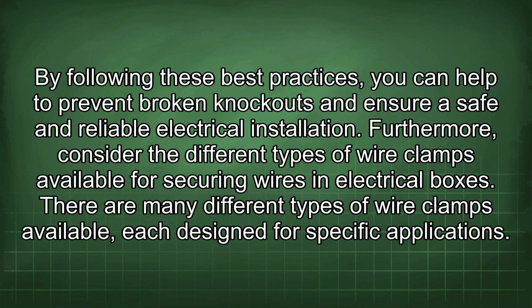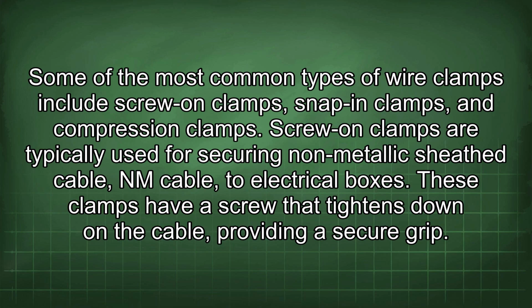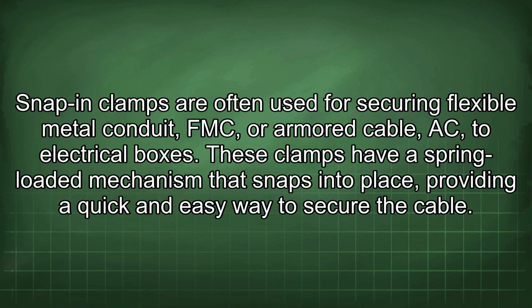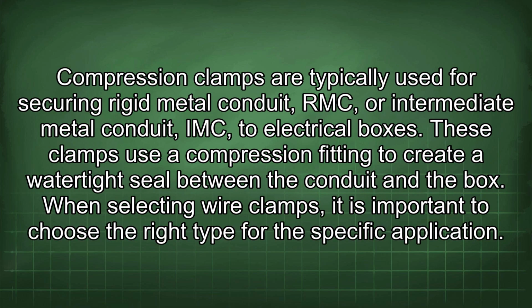There are many different types of wire clamps available, each designed for specific applications. Some of the most common types of wire clamps include screw-on clamps, snap-in clamps, and compression clamps. Screw-on clamps are typically used for securing non-metallic sheathed cable, NM cable, to electrical boxes. These clamps have a screw that tightens down on the cable, providing a secure grip. Snap-in clamps are often used for securing flexible metal conduit, FMC, or armored cable, AC, to electrical boxes. These clamps have a spring-loaded mechanism that snaps into place, providing a quick and easy way to secure the cable. Compression clamps are typically used for securing rigid metal conduit, RMC, or intermediate metal conduit, IMC, to electrical boxes. These clamps use a compression fitting to create a watertight seal between the conduit and the box.